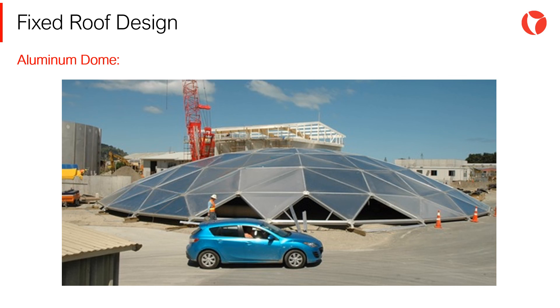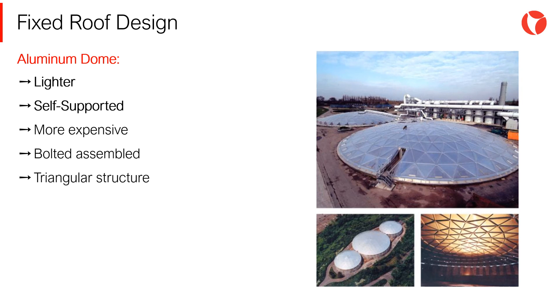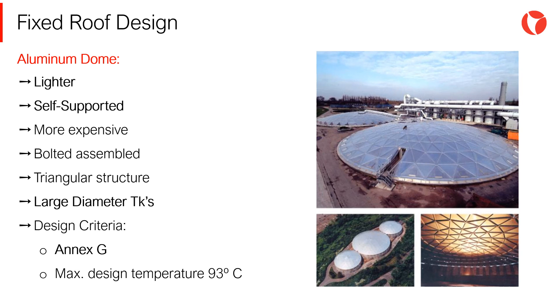A very good alternative are aluminum dome roofs, like the one shown on screen. Aluminum dome roofs are lighter, self-supported, and obviously more expensive than other types of roofs due to labor costs and material. They are bolted assembled and have a triangular structure for rigidity reasons. Normally they are used for large diameter tanks. The design criteria are indicated in Annex G of the API 650 code, where the maximum design temperature cannot exceed 93 degrees Celsius.